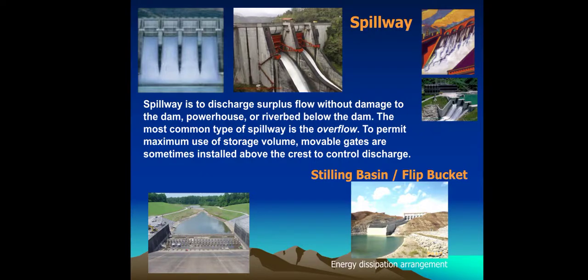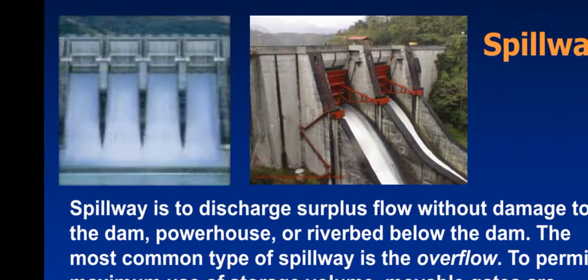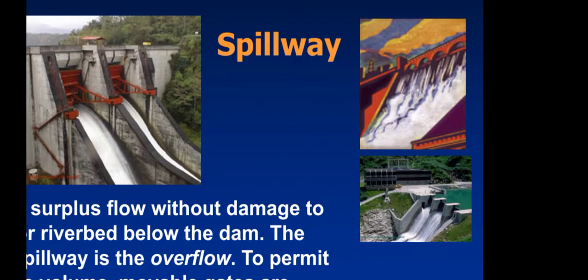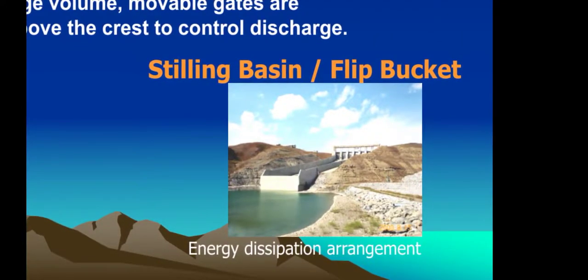Spillway: A spillway is used to discharge surplus flow without damage to the dam, powerhouse, or riverbed below the dam. The most common type of spillway is the overflow type. To permit maximum use of storage volume, movable gates are sometimes installed above the crest to control discharge. Energy dissipation arrangements include a stilling basin, flip bucket, and energy dissipator.